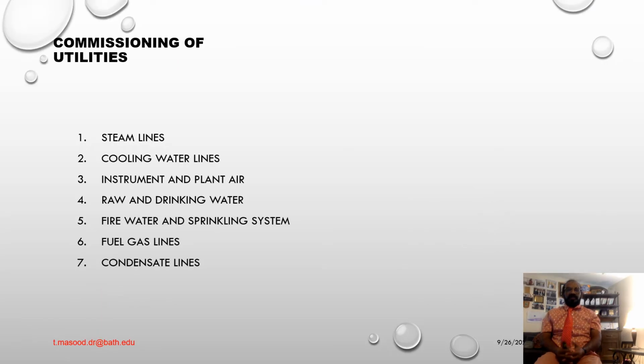topic. Commissioning of utilities: steam lines, cooling water lines, instrument and plant air, raw and drinking water, fire water and sprinkling system, fuel gas system and condensate lines. Various utilities such as steam and cooling water, whatever I have explained just now, must be put in service. Prior to commissioning, the various lines must be tested for leakage and cleared of debris and construction materials. The latter may be done by water circulation and steam or air blowing techniques depending on the particular utility service. Such techniques are generally described in different ways on different parts of the utility system.